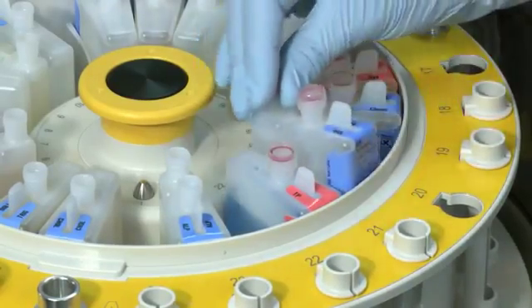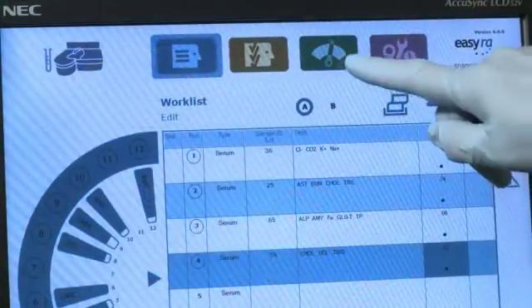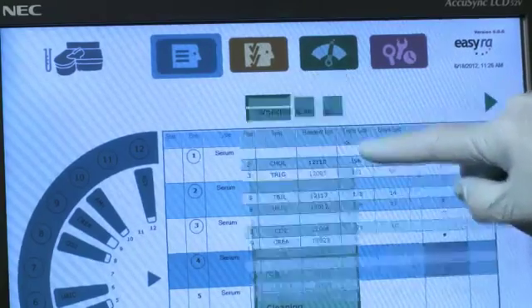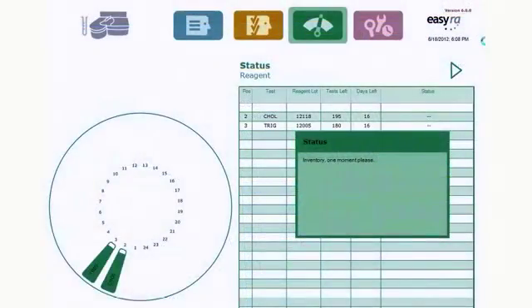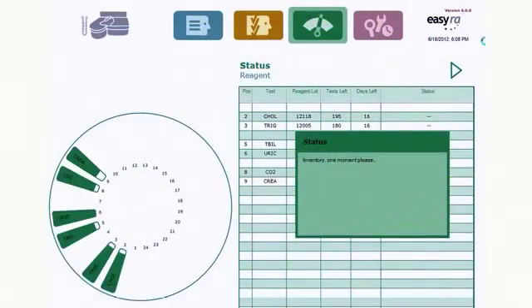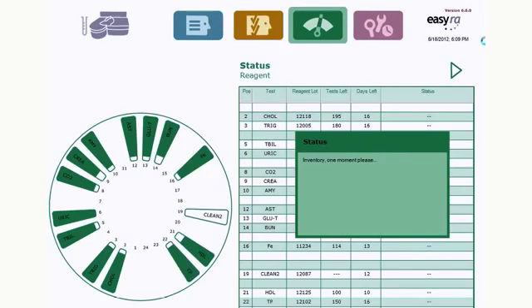Simply place a smart reagent wedge on the analyzer, and EasyRA identifies reagent locations, number of samples remaining, sample volumes, and expiration dates. Two-way communication between the analyzer and reagent wedges allows for continuous updating, providing real-time inventory control.